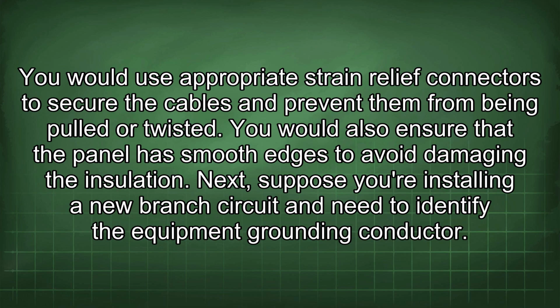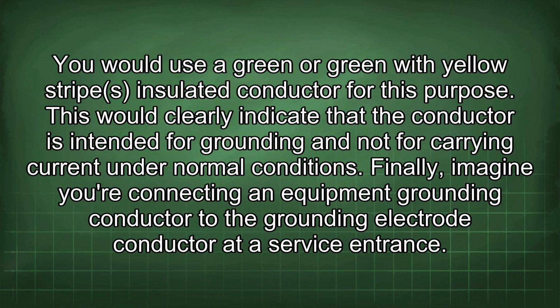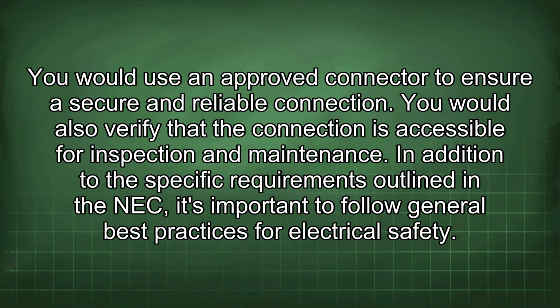Next, suppose you're installing a new branch circuit and need to identify the equipment grounding conductor. You would use a green or green with yellow striped insulated conductor for this purpose. This would clearly indicate that the conductor is intended for grounding and not for carrying current under normal conditions. Finally, imagine you're connecting an equipment grounding conductor to the grounding electrode conductor at a service entrance. You would use an approved connector to ensure a secure and reliable connection. You would also verify that the connection is accessible for inspection and maintenance.